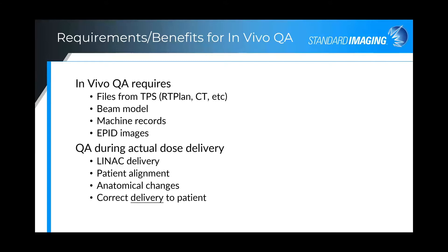Requirements for Adaptivo's in vivo analysis are the portal images, files from your treatment planning system such as the RT plan and planning CT, as well as the pre-configured beam model customized to your linac. Adaptivo also utilizes the EPID images and machine records associated with the delivery. In vivo QA has many benefits, including measurement during the actual delivery, the ability to QA patient alignment during treatment, and monitoring anatomical changes — all of which help ensure accurate dose delivery to the patient.